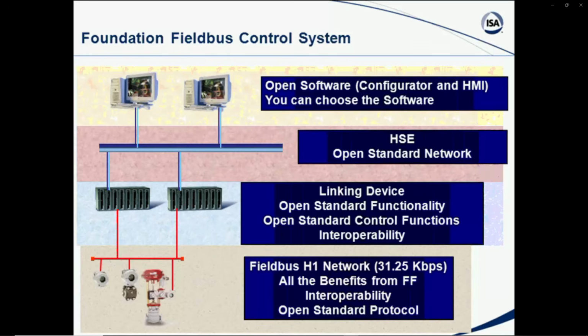In the field, you have the H1 network, and you have the Foundation Fieldbus interoperability, open standard, so that you can use many different types of transmitters, controllers, IPs, different types of equipment. And again, by using the Foundation Fieldbus, getting that information back into the control function, you can save a tremendous amount of wiring. You can actually, if you want to, also we mentioned earlier, you can truly move the control right out to these locations.